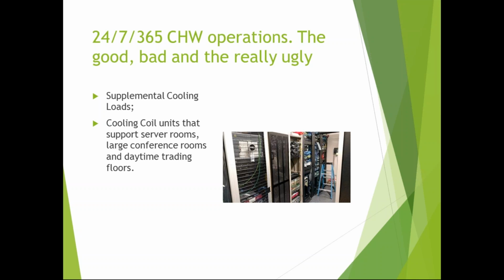Well, that didn't work here because my condenser water system is pretty small compared to the building - it only goes two floors, between the third mechanical space and the first mechanical space on the ground floor. Condenser water only supports my central chilled water plant. My chilled water pumps up a chilled water riser, and that's tapped off to a fan coil unit - basically like a radiator with air blowing. It takes the heat from inside the server rooms and transfers it to the cooling coil, which goes through our chillers, condenser water, out the towers.